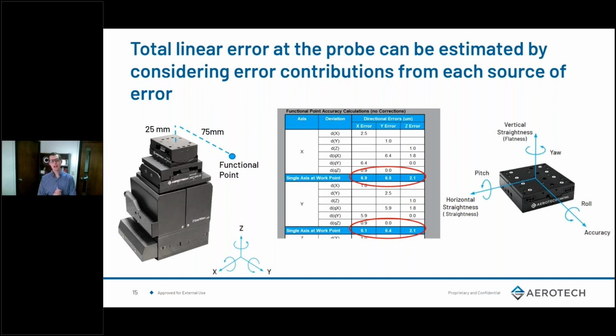This is where you need to ask your precision motion supplier about their calibration capabilities. Typically, the accuracy is not that important in optical alignments. However, with this trench level optical alignment, the edge coupling at the wafer level in a trench, the accuracy is important because as you do an insertion angle adjustment, your linear axes are moving over larger travels, and these directional errors are amplified at your work point. We can calibrate if we know the position of your probe with respect to the mounting surface. We can calibrate with our optic at that point and essentially remove most, if not all, of the error associated with the amplification over the moment arm.